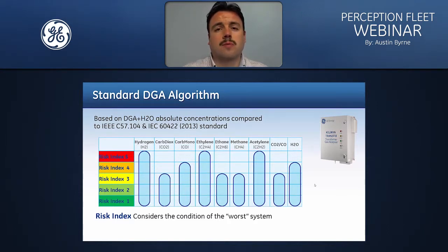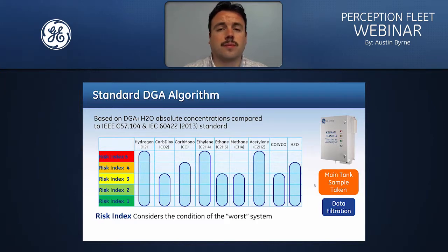So whenever the online monitor takes a sample from the main tank, data filtration is applied on that data, and that's to ensure that no spurious information is passed through into the algorithm. So our intelligent analytics engine removes what it regards as spurious data. That could be, for example, if there's a spike in hydrogen and the next reading of hydrogen does not show the same level of hydrogen gas, then the initial spike will be ignored for purpose of the evaluation.